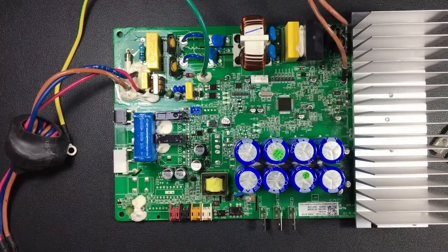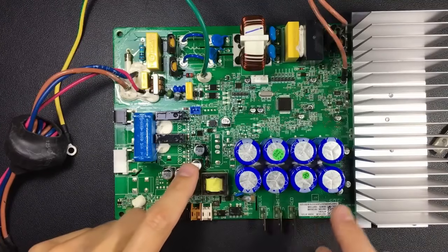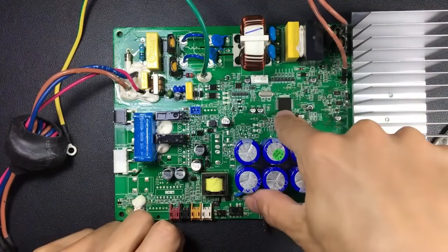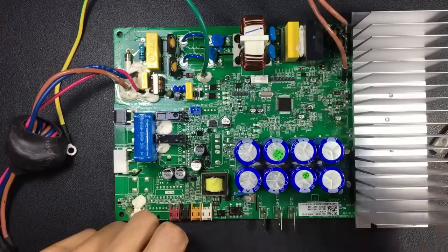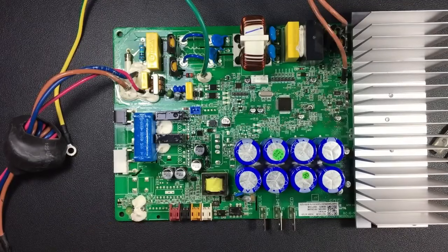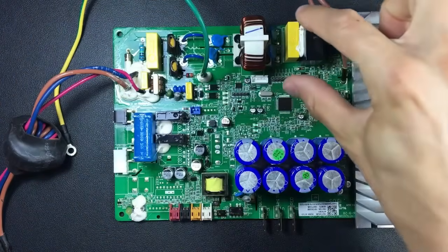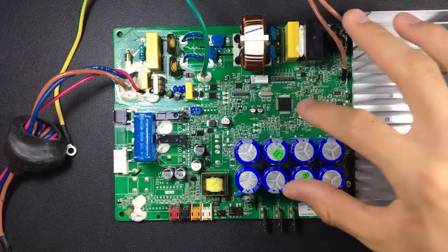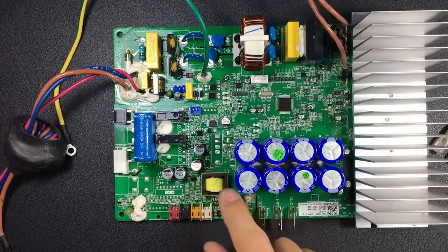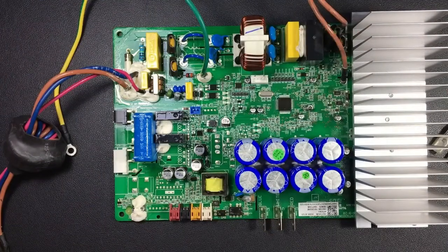Any problem in the source area means the electronic board directly does not work, because this is what prepares the voltage to power the microprocessor that commands everything else and warns us of error codes. Everything we've seen—the rectifier, capacitors, and switched source—is part of the source that powers the control zone.